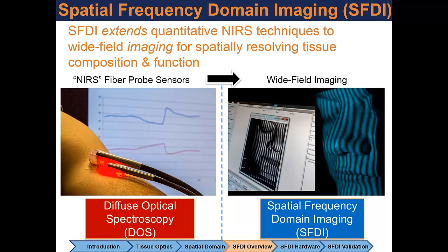Effectively, in the early days we wanted to avoid the problem by using just near-infrared light, but even that wasn't good enough, and we've since added visible light in combination with near-infrared light in order to more fully characterize the problem, where we calculate melanin, oxy- and deoxyhemoglobin, water, and scattering all simultaneously. And so to measure one, we like to measure all.